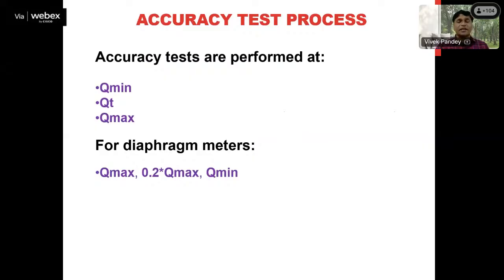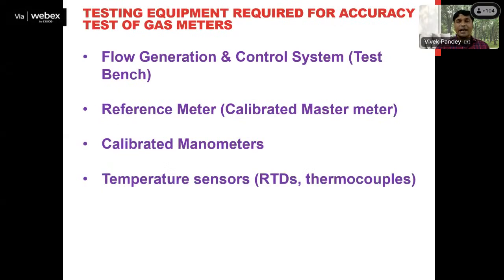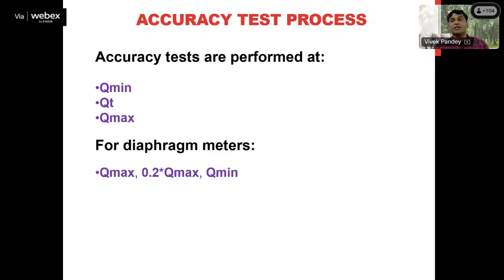Apart from these three readings, a particular LMO or the enforcement official can perform more tests at other flow rates also, but it should be within what? Minimum to maximum flow rates. Fine. For diaphragm meters, the flow rates specified for the accuracy test are minimum flow rate 0.2 times Q maximum, and Q maximum. And as I already mentioned, diaphragm meters are mostly used as domestic gas meters.